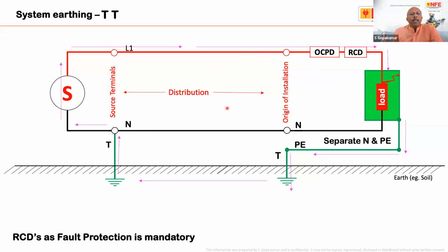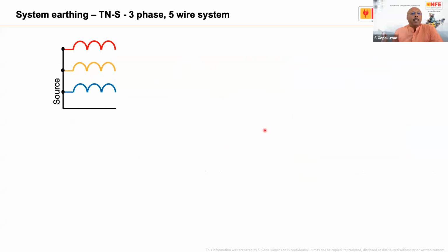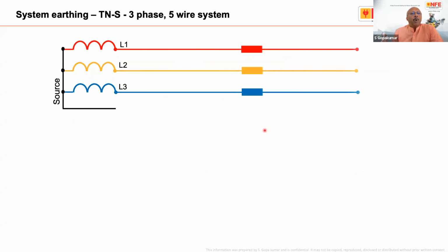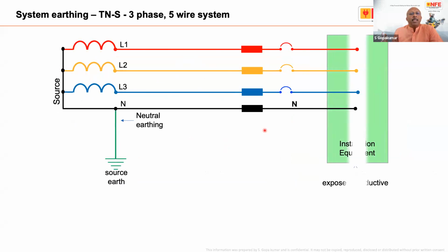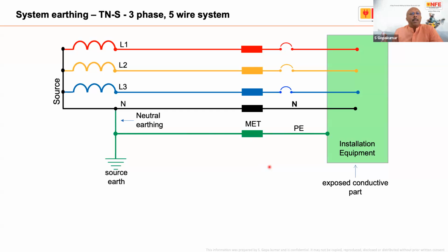Second point, if we look at our rules, regulations, CEA regulations or the codal requirements of the standard, TT is not recommended for India. Unfortunately, we follow this all over India. I really don't know where it started. So then what do we do? We have to make our installation a TN-S. This is the actual requirement in the standard.